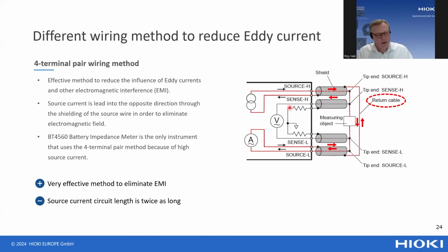There is, however, also a disadvantage to this wiring method. If you look here, the source current travels first through the battery and then back to the battery tester, and then once again goes through the shielding, through this return cable, back to the shielding of the other coaxial cable and back to the measuring instrument. This is a distance twice as long as with the standard twisting solution—the standard 4-wire measurement method.